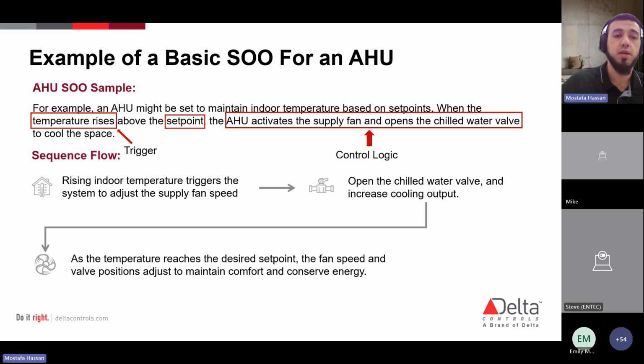It's a very basic concept. So because the temperature rises above the set point, you know, there's your set point, and this is probably referencing, it's pretty obvious, the indoor temperature, right? So as the indoor temperature rises above a specific value that's calibrated at the controller, the air handling unit will activate the supply fan and open the chilled water valve. There's your control logic or your response, right? So those are the steps that the system is going to take to get back to that optimal indoor temperature. Right. So very basic. You have rising indoor temperature. The system is going to open the chilled water valve and increase the cooling, right?